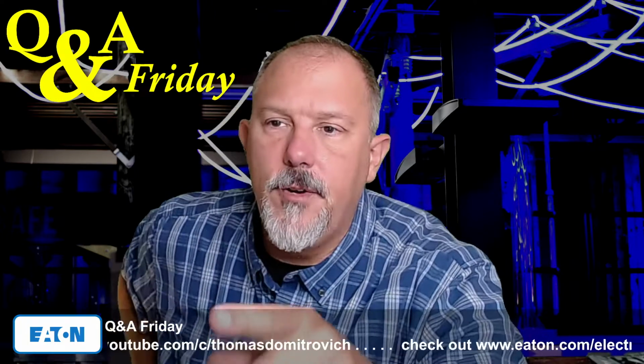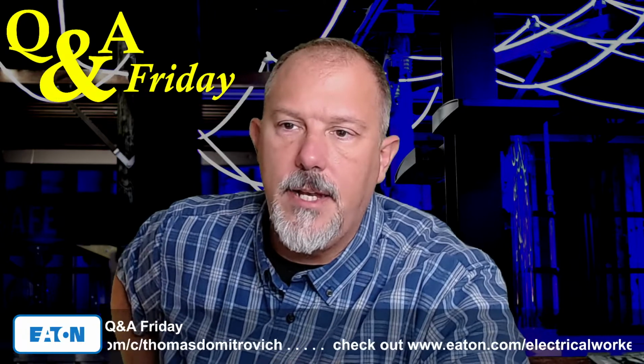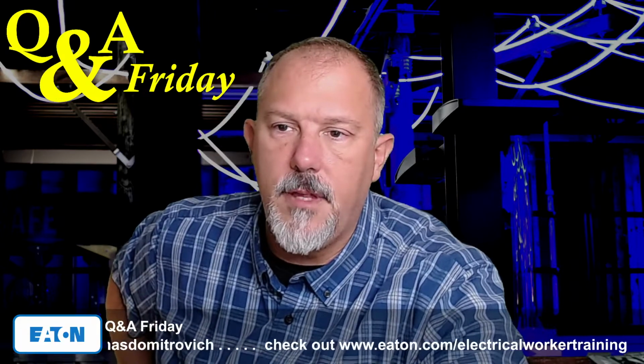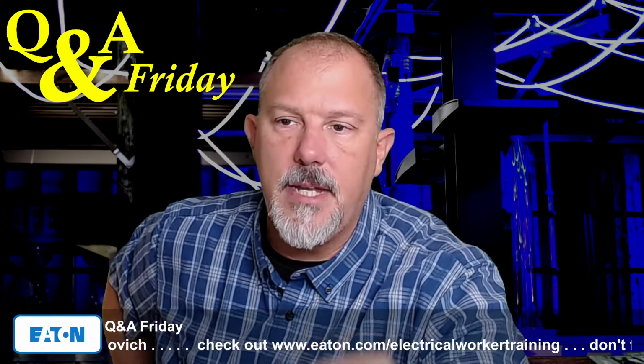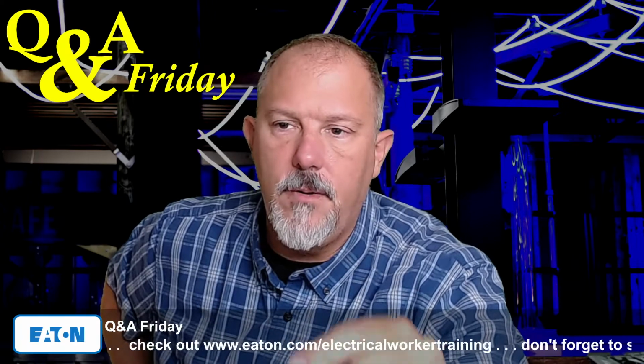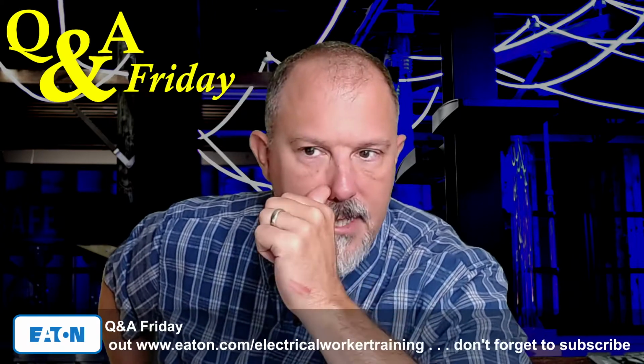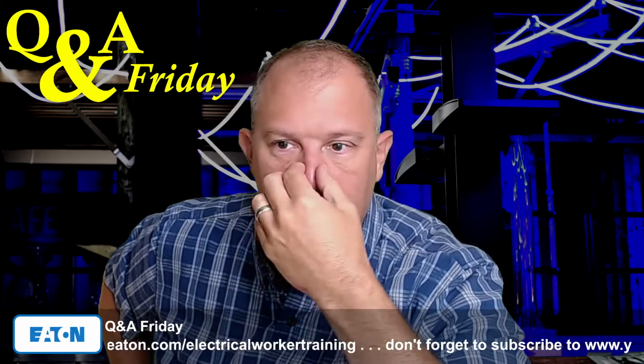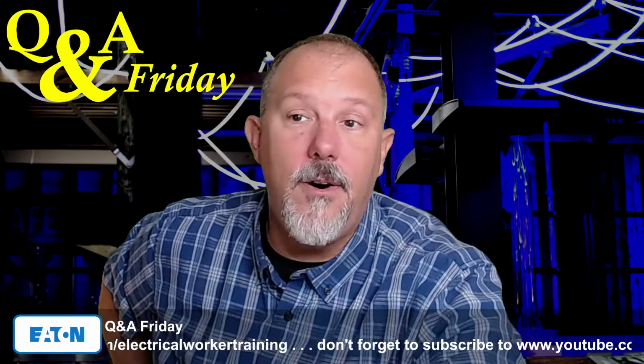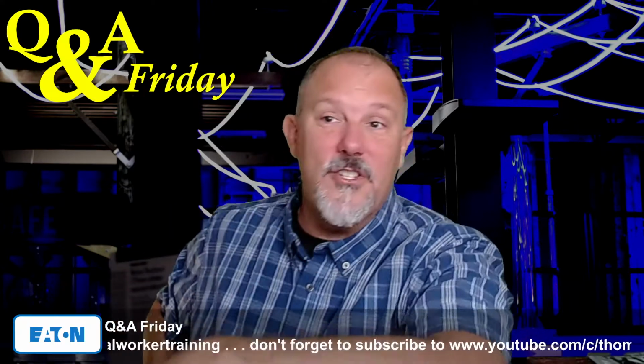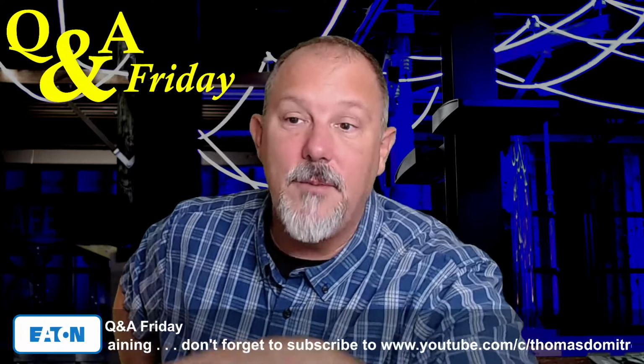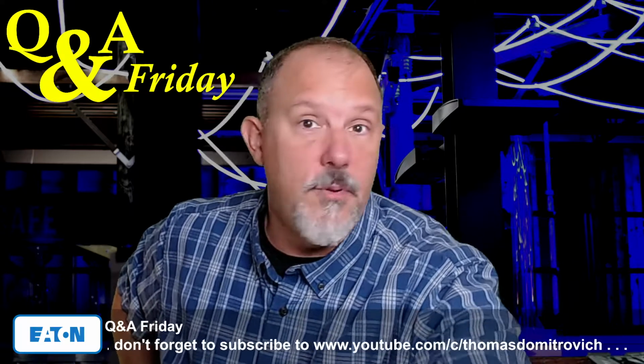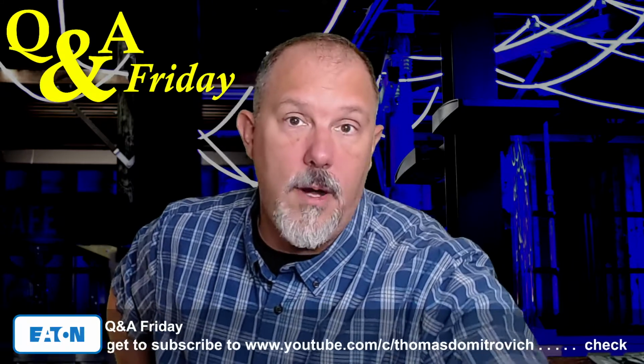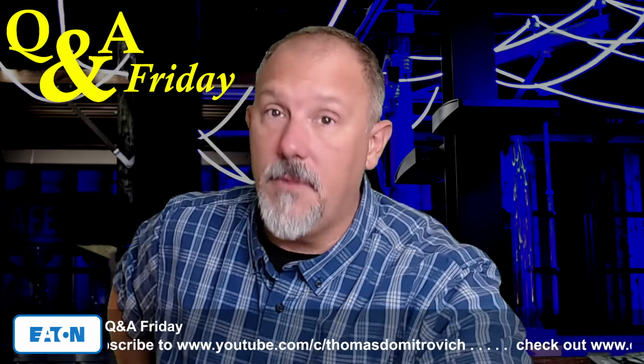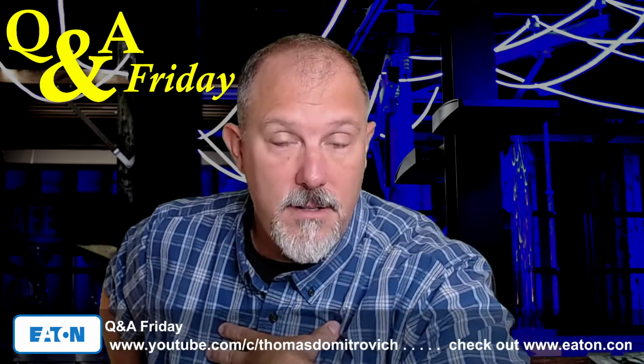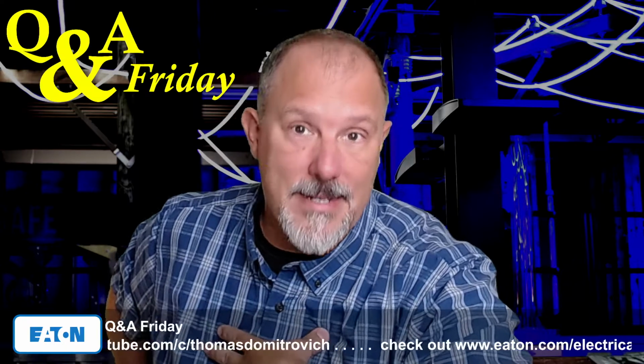And L says, we are using EYS fittings in non-hazardous locations with a sealant other than what is required by the manufacturer to mitigate the passage of airflow. Is it okay to use this fitting outside of its listing as long as it's approved by the AHJ? Well, L, I know this is not necessarily a medium voltage discussion, but just to address that, I would say, L, the AHJ can approve anything, right, that they want, but they're going to have to use something, in my opinion, to justify why they would be accepting it.